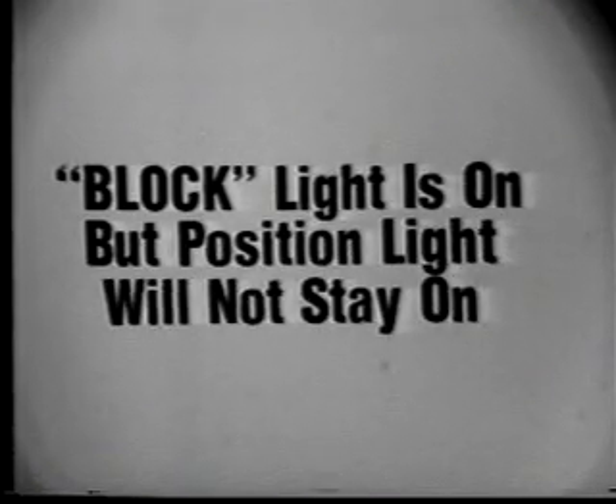Next, we will consider what items to check when the following situation occurs. A function is in either the open or closed position and the block button is pushed. The function operates properly and the block light comes on, but the open or closed position light does not stay on, indicating the position of the function. The problem will most likely be found in the memory circuit, which is located in the mini panel.